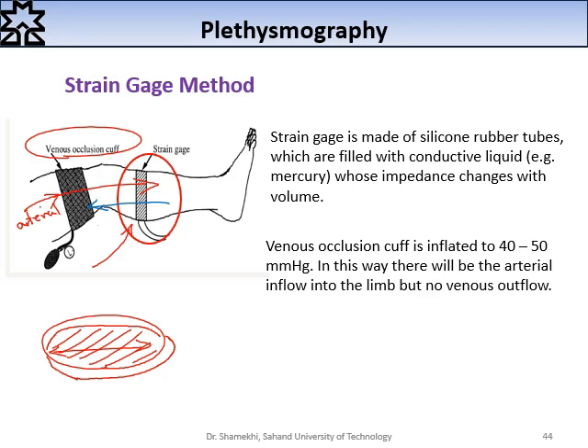the volume after this occlusion cuff will increase for each pulse. We have a curve like this. For each pulse, the volume of the limb under the venous occlusion cuff will be increased. And this volume increase leads to an increase in the radius of this strain gauge around the leg, and now we can measure the volume change in this limb.